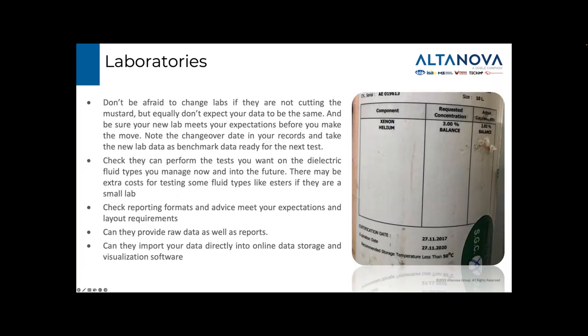In this picture, the carrier gas bottle was discovered connected to a DGA gas chromatography machine. It was using a helium xenon mix, and it was being used as a carrier gas. For gas chromatography used in DGA analysis, helium should be a minimum of 99.999% pure, also called grade 5, for such an application. DGA data will be useless with this carrier gas and may even damage the equipment. This quality of helium is about right for filling party balloons.